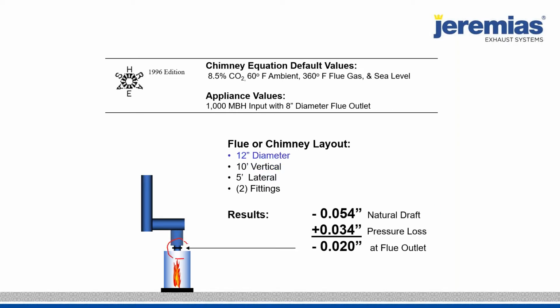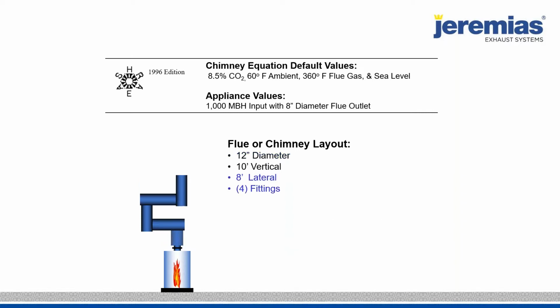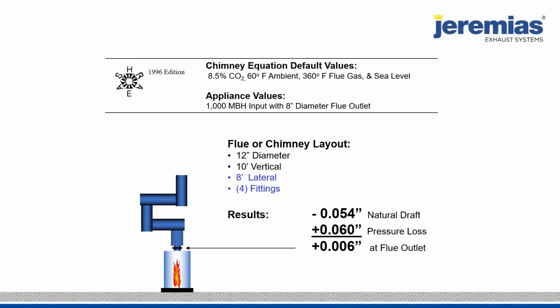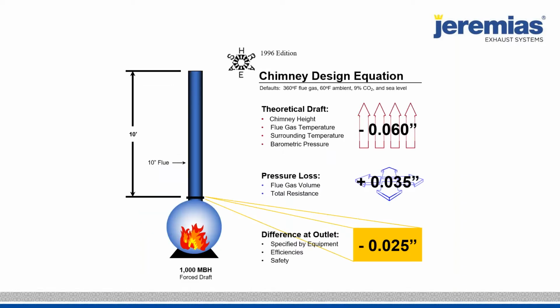We have an 8 to 12 increaser right there, and this heater is thinking like it's going straight up 20 feet with an 8-inch diameter vent. So these are actually some real numbers. We kind of laugh about this. Only contractors would actually see this, but theoretically you have to increase to 14. We would stop at 12. We don't increase the sizes more than 2 sizes because of simple velocity sake and some rules of thumb in the National Fuel Gas Code. But this is just a quick example.